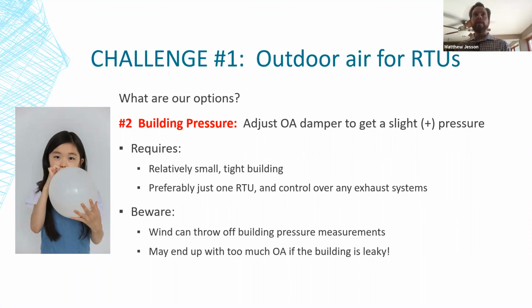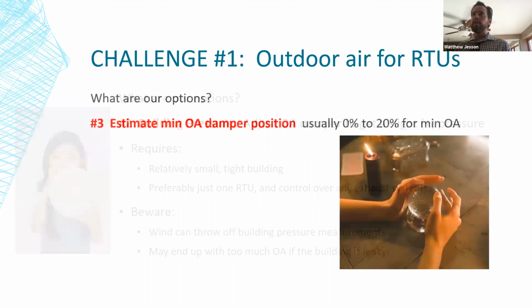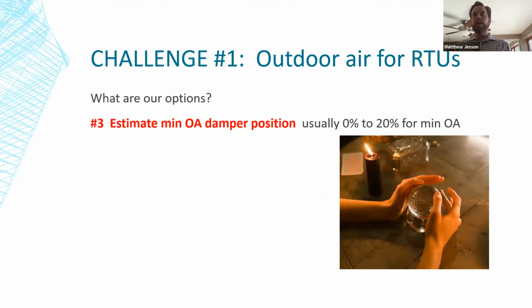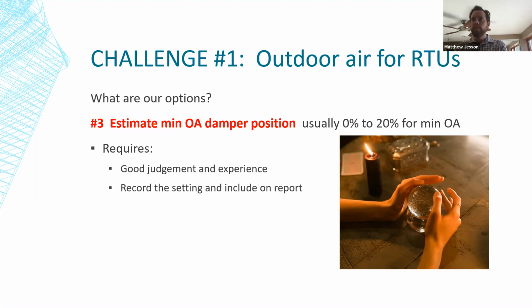So that's where kind of the next method comes into place, and that's, you can make an educated guess, estimate what that minimum outdoor air damper position should be. Usually a minimum outdoor air on a rooftop is going to be somewhere between 0 and 20%. And I say 0 because most of those dampers, even if they're fully closed, will get some airflow through them. There's some leakage, and in some cases, that could be 5% of your supply air. So if you have experience in TAB, you might have some rules of thumb developed that say 0% gets you 5%, 5% gets you 10%, by which I mean a 5% damper position gets you 10% of your supply air through the minimum outdoor air.